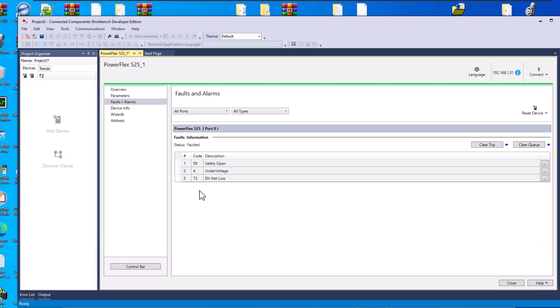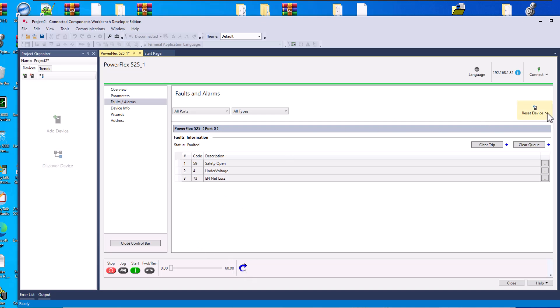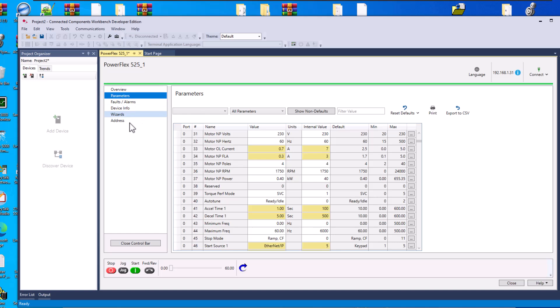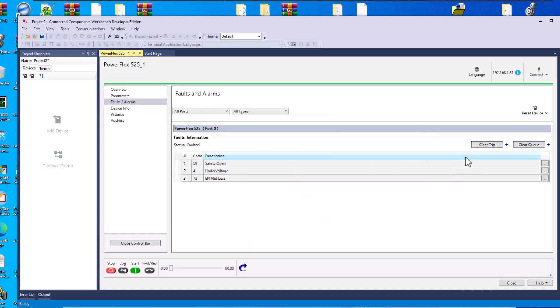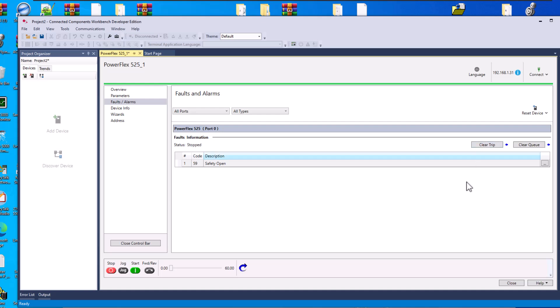That's a very helpful tool. When you pull the e-stop back out, you can clear the fault. You can come in and take control of it. Just keep in mind resetting the drive resets to defaults, so don't do that. You can come over here and reset the drive if you want to. Let's go into faults and clear trip - that clears the trip. So clear trip is going to reset that, but clearing your queue is going to get rid of all the stuff in the queue. If you hit this it's going to get rid of everything, so now if I hit the e-stop again the only thing in there is going to be that e-stop, and then you can clear that queue right here.